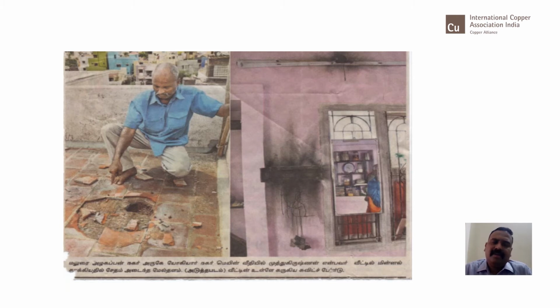So when people say, okay, we want an external lightning protection, then we ask, why do you want external lightning protection? They say, okay, if I avoid a strike happening on the building, all my problems will be solved. Now, to better understand this, I'm going to present a case study here. This accident happened in the south of Tamil Nadu, where there was a lightning strike on top of a building, and this building did not have lightning protection. It came in the newspaper saying that there was a strike on the structure, and probably the current went through the reinforcement rods, and inside, the equipment boards failed.